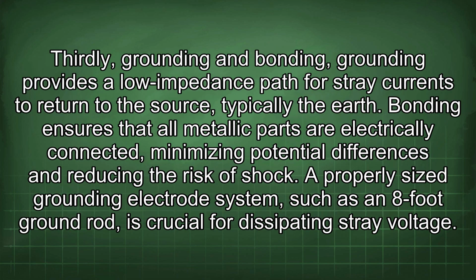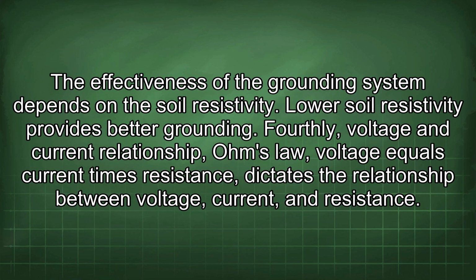Thirdly, grounding and bonding. Grounding provides a low impedance path for stray currents to return to the source, typically the earth. Bonding ensures that all metallic parts are electrically connected, minimizing potential differences and reducing the risk of shock. A properly sized grounding electrode system, such as an 8-foot ground rod, is crucial for dissipating stray voltage. The effectiveness of the grounding system depends on the soil resistivity. Lower soil resistivity provides better grounding.